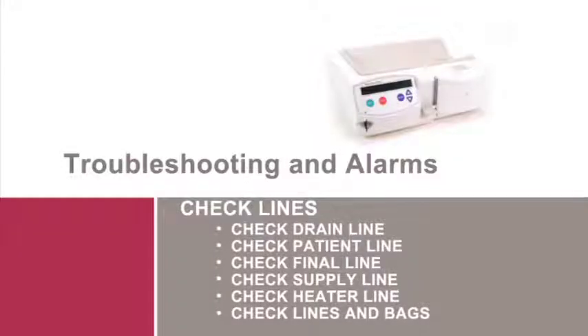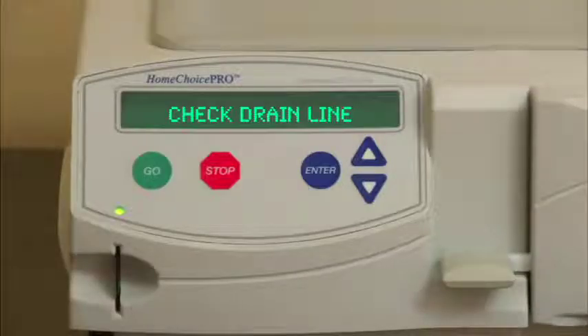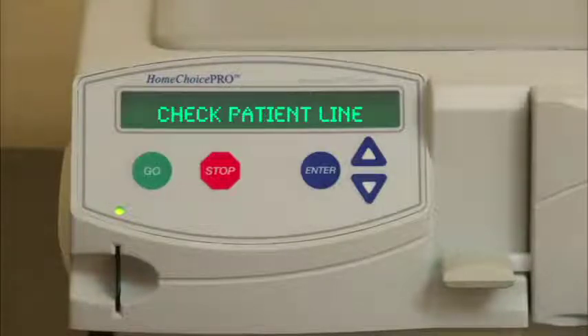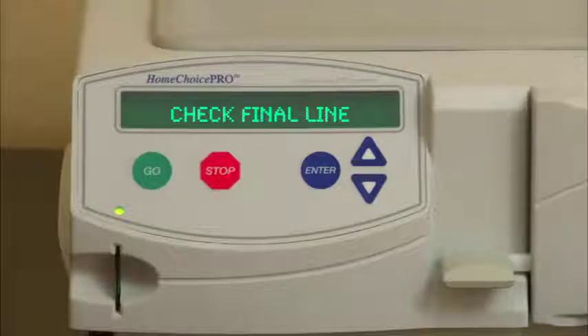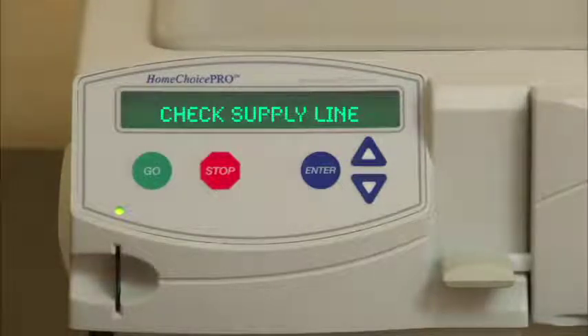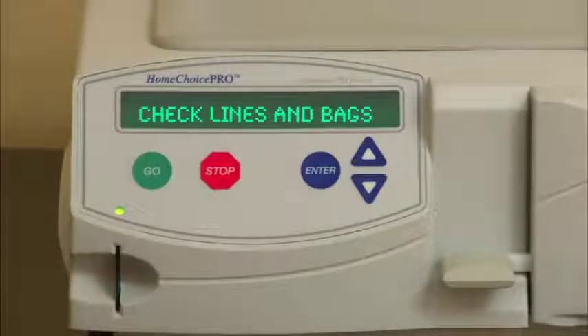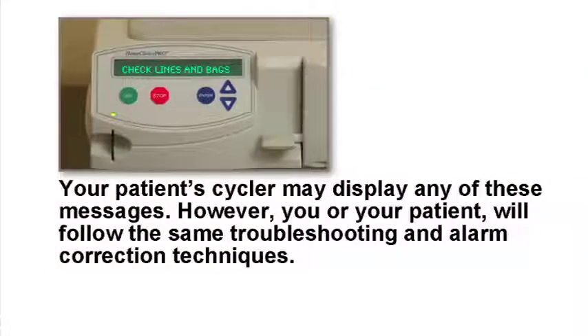Troubleshooting and alarms. Check lines. The 6 check line alarms are: check drain line, check patient line, check final line, check supply line, check heater line, check lines and bags. Your patient cycler may display any of these messages. However, you or your patient will follow the same troubleshooting and alarm correction techniques.